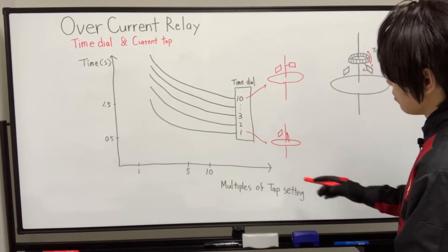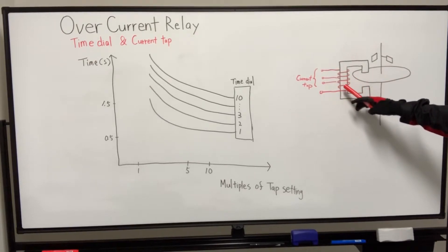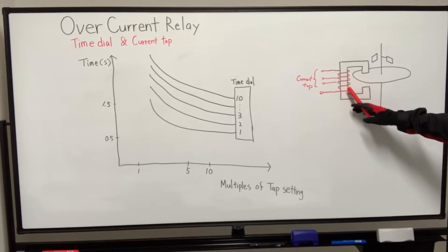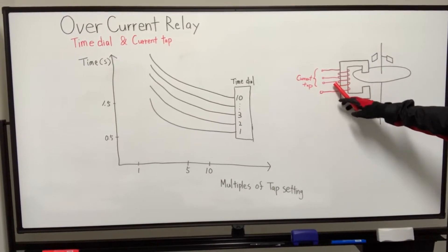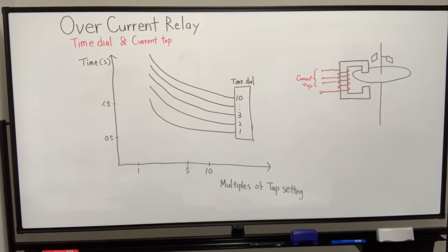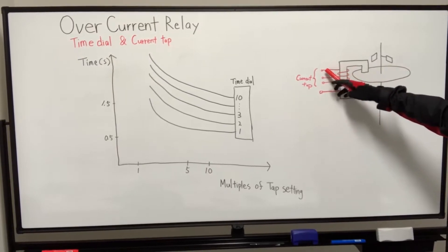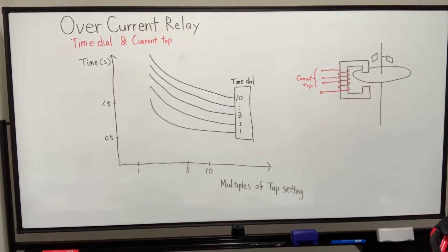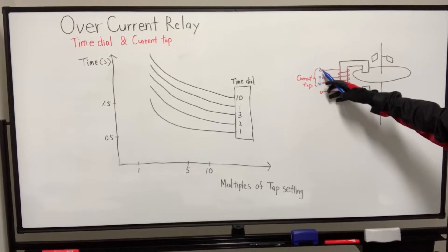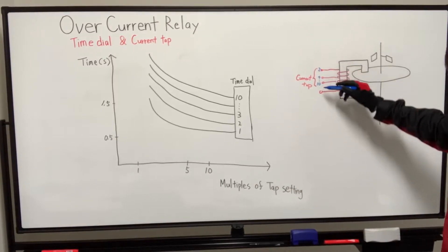This diagram represents the construction of the relay including current tap. The fault current that is fed to the coil is controlled with these current taps, which allow pickup current setting. There are two terminals here - one side is fixed, and another side is connected to each tap. So this is the setting number: tap setting number 2, 4, and so on to 10.